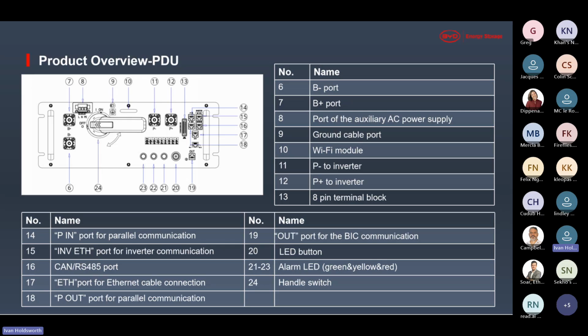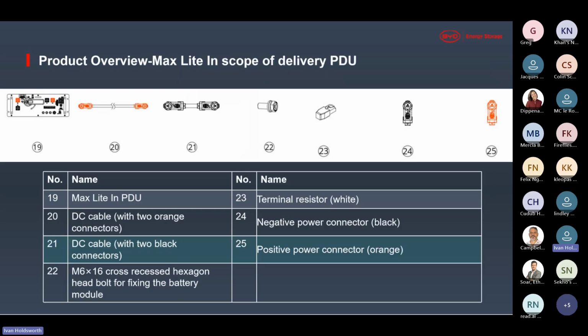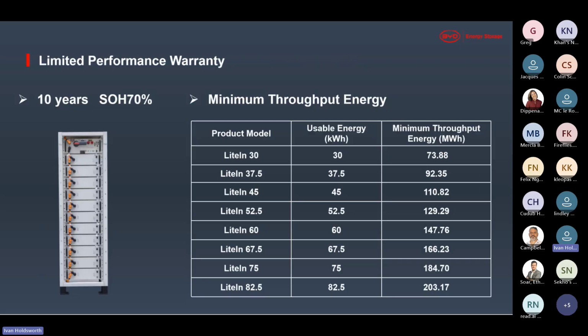And then on your communication side, all your communications on the top right, that's your parallel communications, your inverter communications, and your internet monitoring. Then number 19 will be your cable to your BICs, and that daisy chains down to the bottom module. What you get in the box, you get your cables, your power cables on the left to connect your tower modules, and termination resistors. It's very important to keep in mind the color of the termination resistors. I'll get to that in a moment.